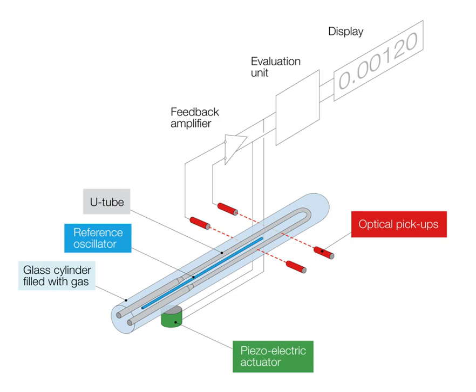The oscillator's eigenfrequency is only influenced by the part of the sample that is actually involved in the oscillation. The volume involved in the oscillation is limited by the stationary oscillation knots at the bearing points of the oscillator. If the oscillator is at least filled up to its bearing points, the same precisely defined volume always participates in the oscillation, thus the measured value of the sample's mass can be used to calculate its density.